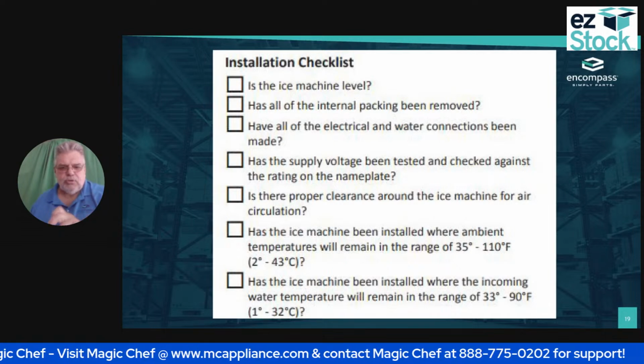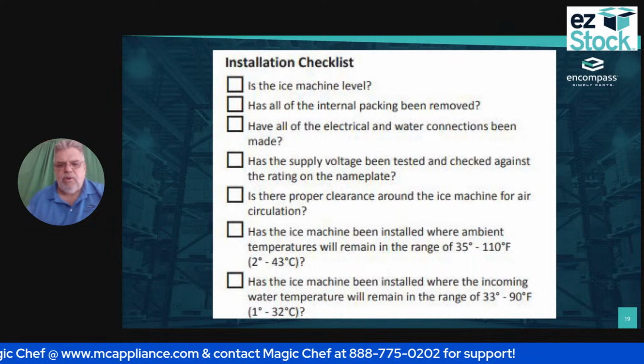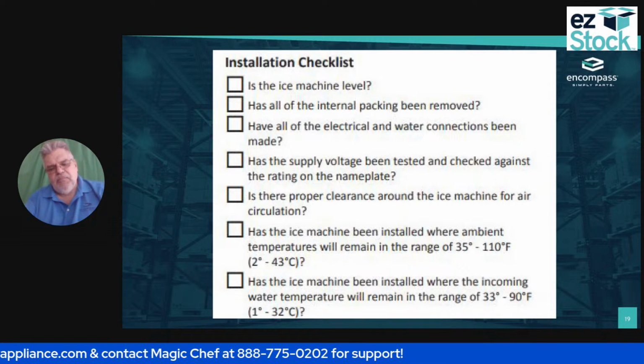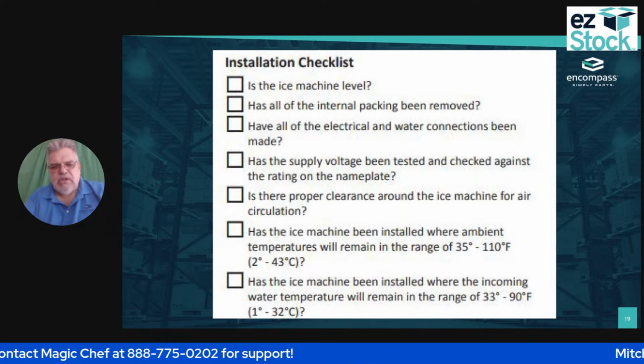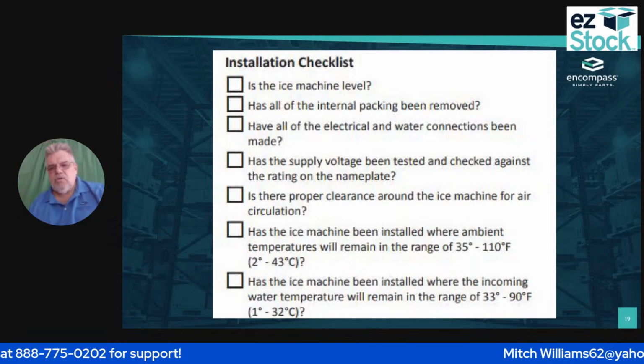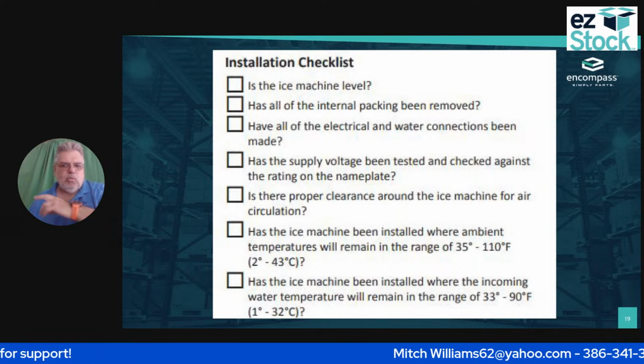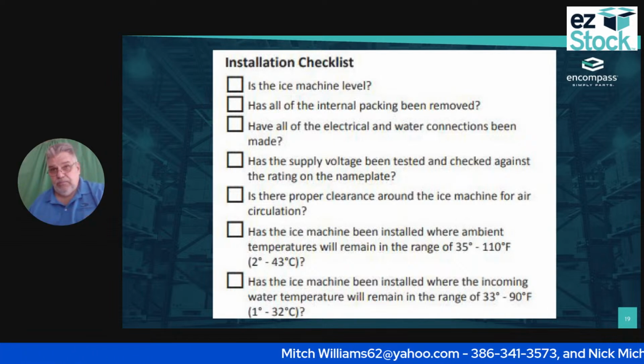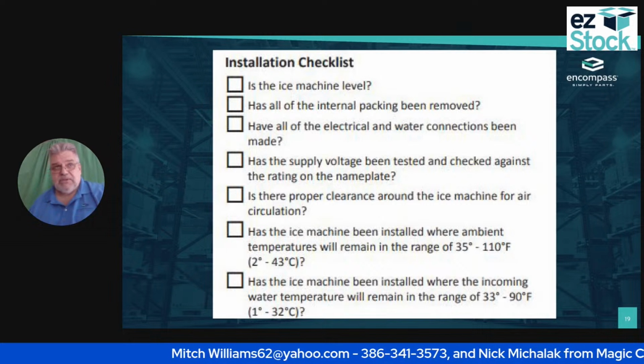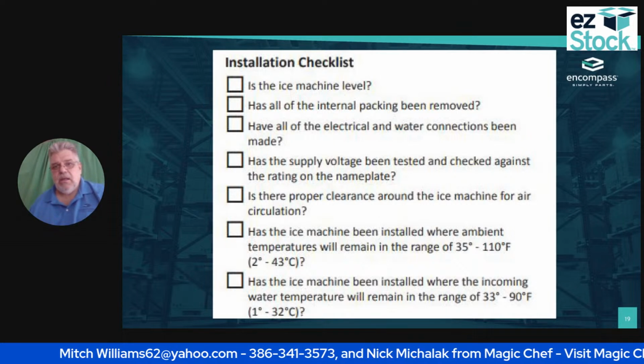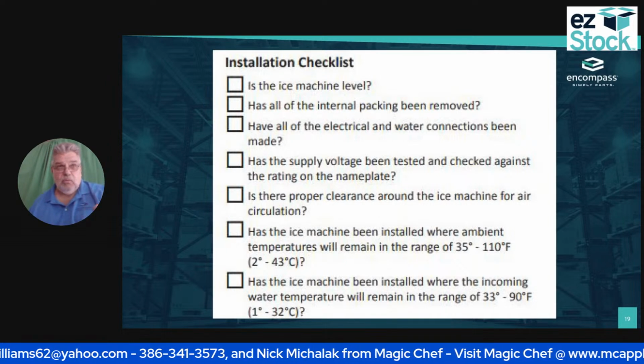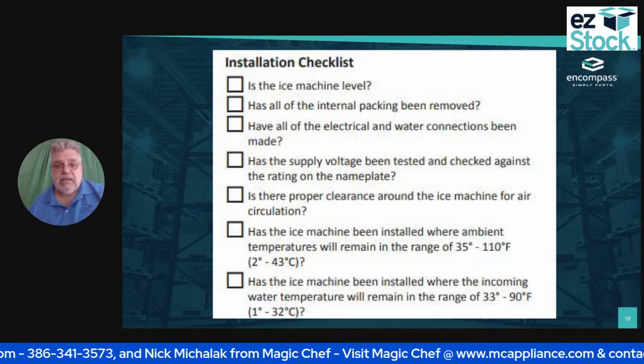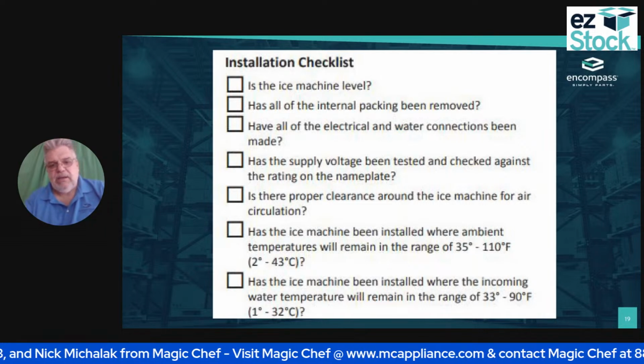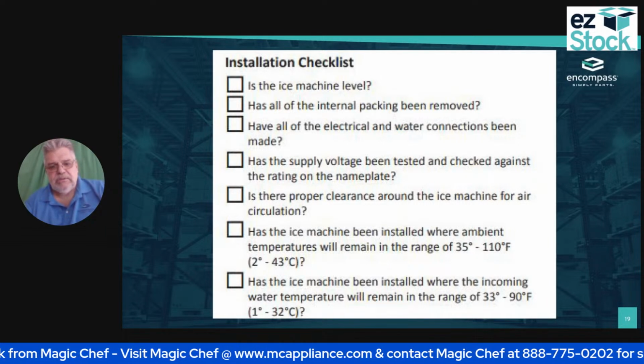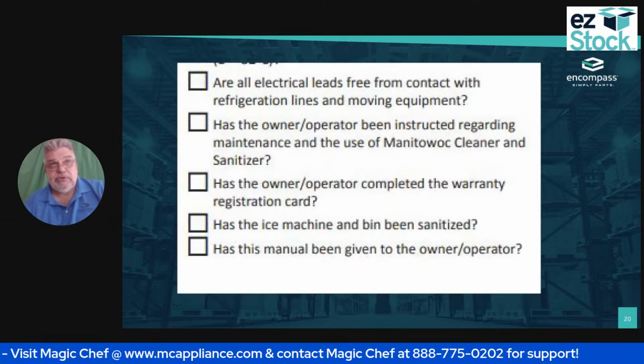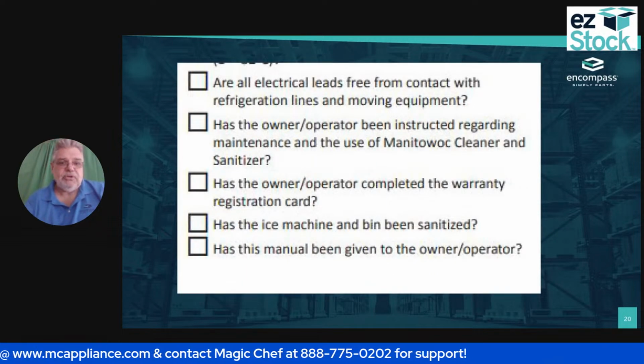Okay, has the ice machine been installed where the water temperature range is between 33 and 90 degrees? A lot of the times there's nothing you can do. The only thing you could possibly do is run that line through some kind of refrigeration, like a cooler, just to help cool it down if I'm at 100-degree water, which is about Miami's water temperature.